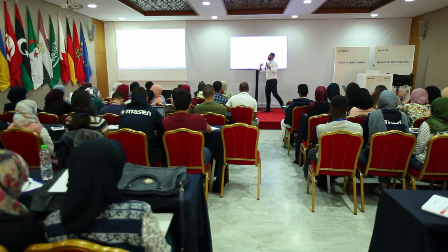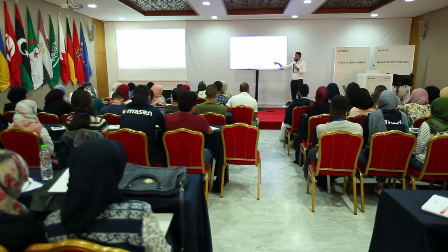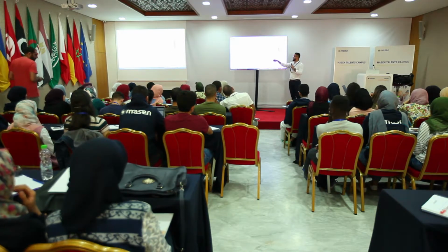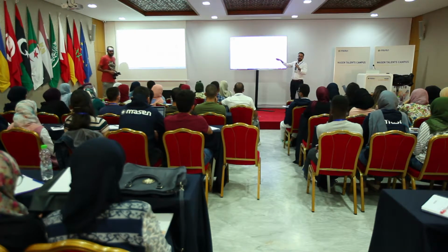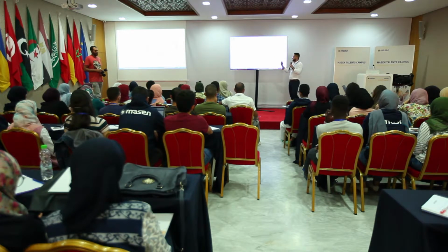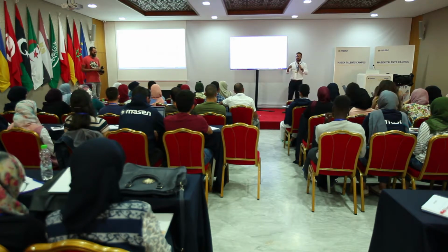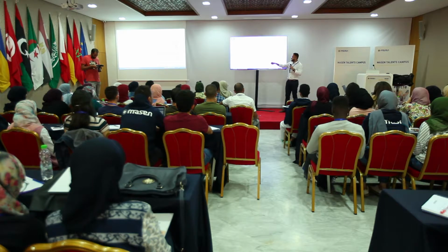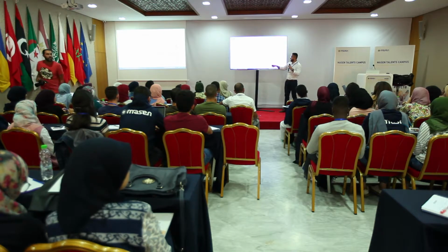But the tank physically, and both the collector and the tank, is the same size. So I'm collecting the same amount of energy from the field and storing the same amount of energy. It's just a matter of the ratio between the power block, the storage, and the solar field. So that's what you need to keep in mind. When people talk about storage, it's good that you keep it in megawatt hour, because then it's really the physical quantity, because hours refers only to how many hours of nominal power I can operate. The relationship you can calculate: if the power block needs this amount of thermal power, times the hours gives me the actual energy stored.